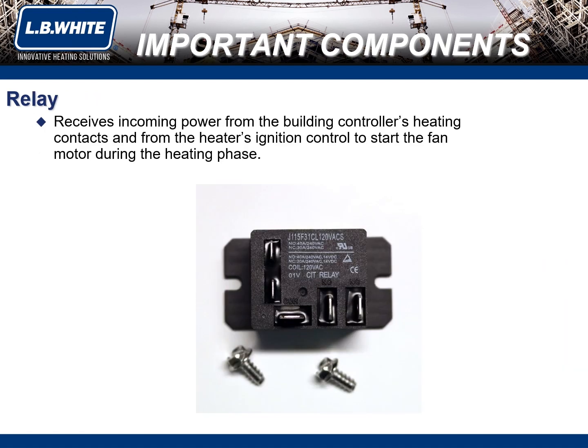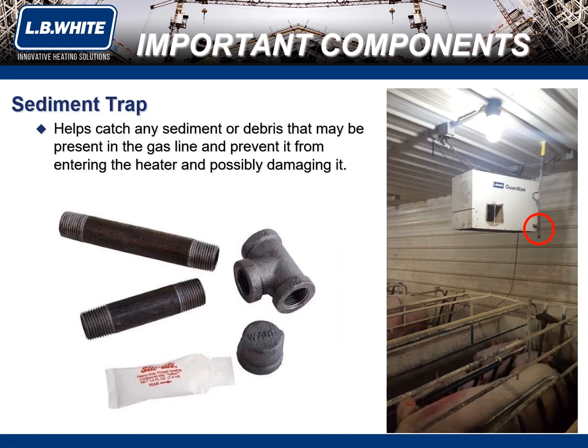A heat relay receives incoming power from the building controller's heating contacts and from the heater's ignition control to start the fan motor during the heating phase. A sediment trap is used to help catch any sediment or debris that may be present in the gas line and prevent it from entering the heater and possibly damaging it.